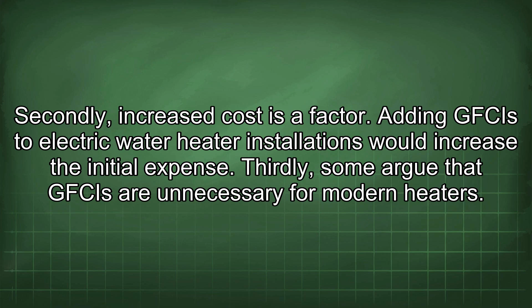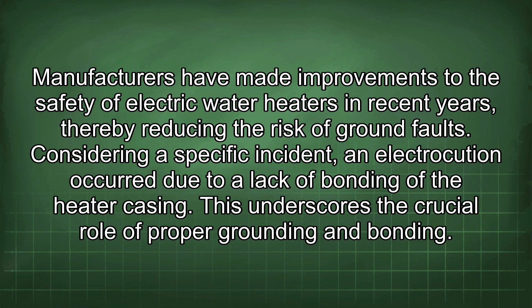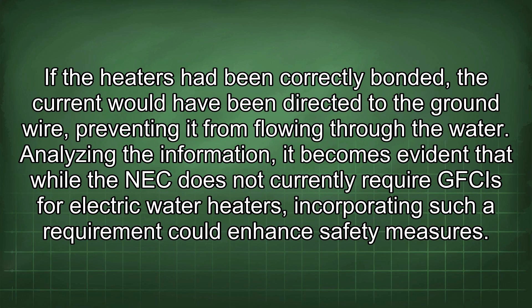Considering a specific incident, an electrocution occurred due to a lack of bonding of the heater casing. This underscores the crucial role of proper grounding and bonding. If the heaters had been correctly bonded, the current would have been directed to the ground wire, preventing it from flowing through the water. Analyzing the information, it becomes evident that while the NEC does not currently require GFCIs for electric water heaters, incorporating such a requirement could enhance safety measures. The described incident emphasizes the potential dangers of inadequate grounding and bonding.